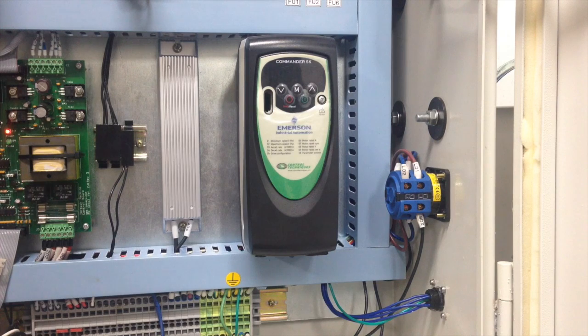Okay? Okay, the first thing you should do is figure out what access level we have for parameter set in the VFD. I don't know what the default setting is. When I first powered mine on, I messed with it. I found that I only had level access 1, which is the basic first 10 parameters that you can see written on the front of the VFD. But I'll show you what I mean and how to change that, okay?